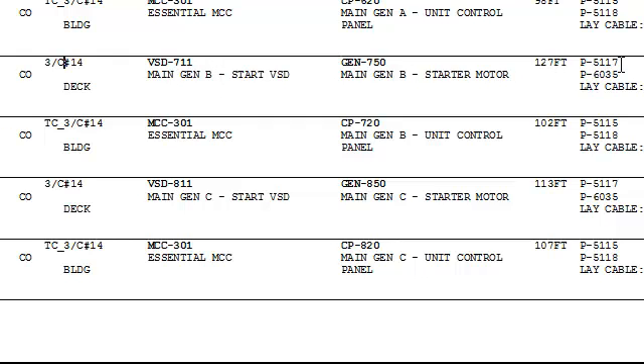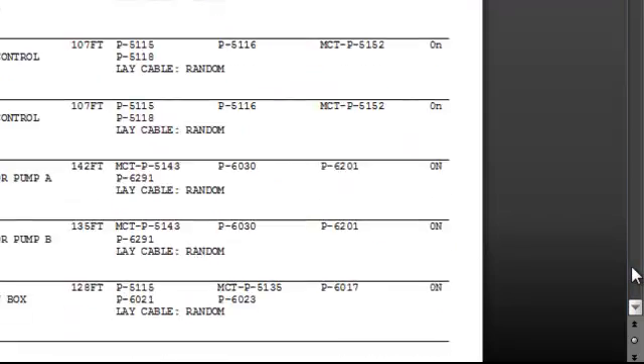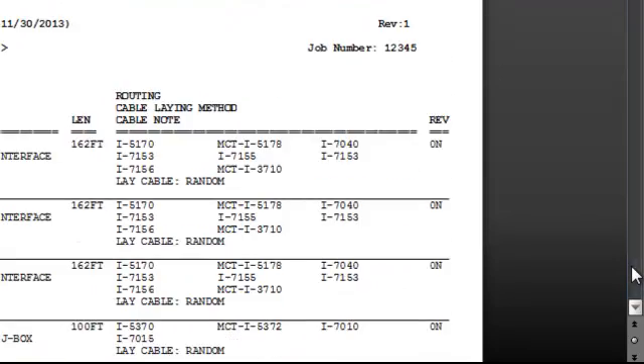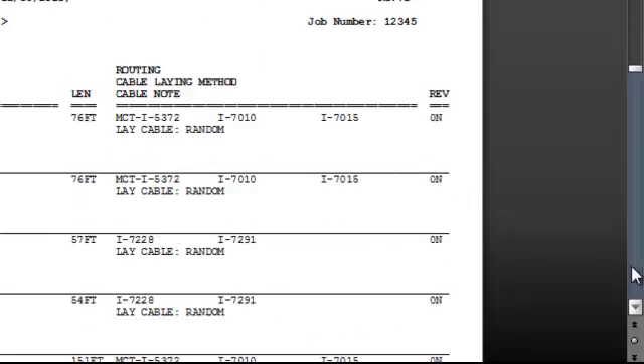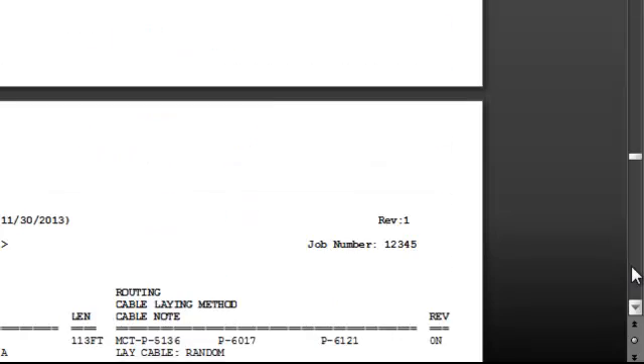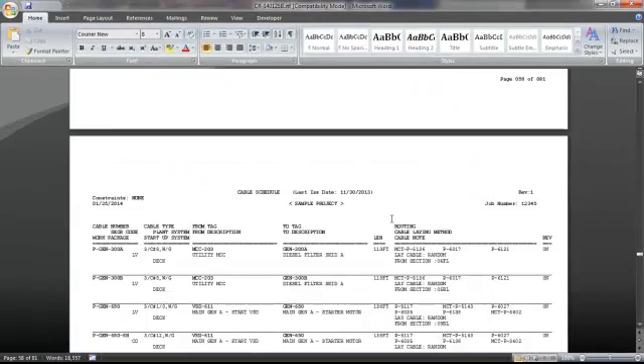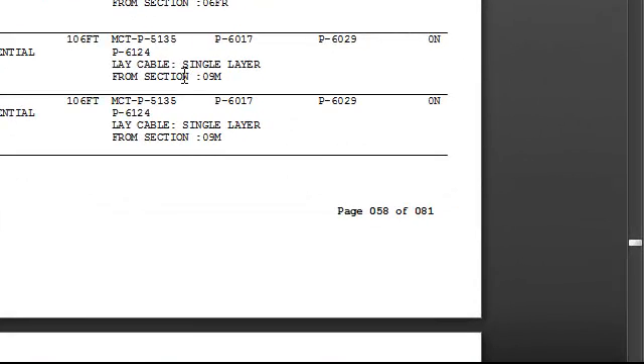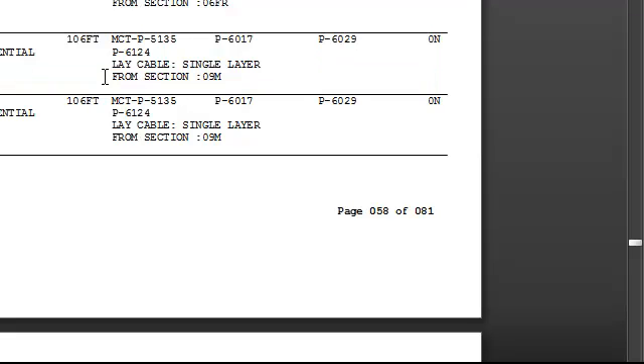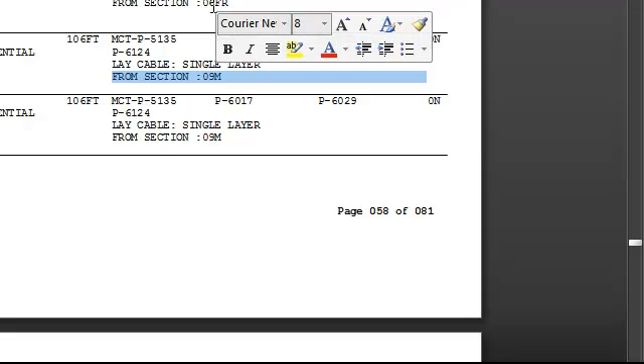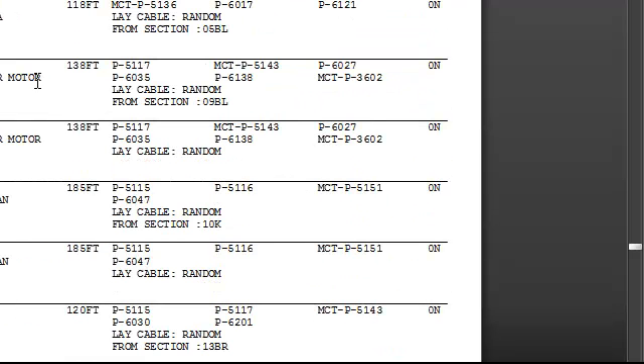Now we're looking at a control cable here. It's a three conductor 14 going from and to, it's 127 feet long. This is the cable tray or the raceways that it is occupying and it is a random lay. In other words it is laid in a bundle. If we go down to some of the bigger cables, I want to get to the power cables because the power cables are going to be a little bigger. Here we go. Here's the three conductor 4 ought. As you know those cables cannot be bundled, those need to be single layer and the program knows that. It's identifying that the cable is installed on single layer. Also I'd like to point out that since this cable was originated in LoadMatic, the motor control center section and actually the bucket 09M is reported for each cable that is originated by LoadMatic.